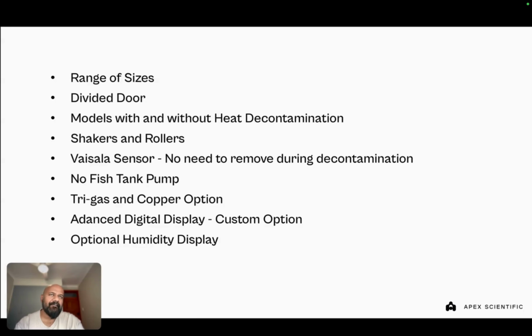Doing some digging, I realized some brands use an aqua fish pump, like you'd use in a fish tank, inside the CO2 incubator. I'm not sure if it's to regulate the CO2 or inject air through a filter. The problem is that this pump has plastic tubing that melts over time, and the pump itself doesn't last very long, especially during decontamination cycles. When it gets damaged they have to replace it. It's a standard fish tank pump you could get locally, but the competitor was buying it through their supplier and charging customers 7 to 8,000 rand just to replace it, on an annual basis.